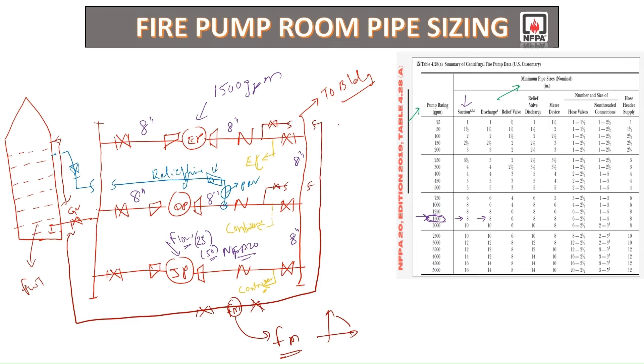Looking at the table for the relief line, we have 6 inch. The pressure relief valve, or PRV, shall be 6 inch, but the relief valve discharge line will be 8 inch as per the table. So we are going to consider an 8 inch relief valve line.